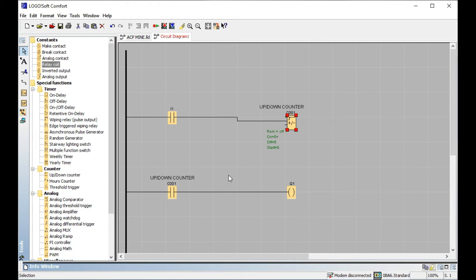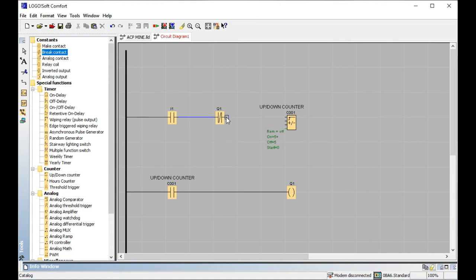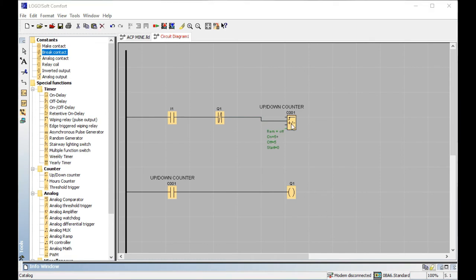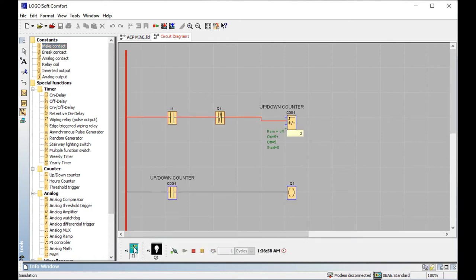This is important for factory safety. For example, on your conveyor belt, if you only want a maximum of ten boxes to pass, you don't want the counter to keep counting beyond that — that would be dangerous for your factory. So I add a break contact for Q1. When the set point of five is reached, this break contact stops further counting. After the set point is reached, the sensor signals are no longer accepted.